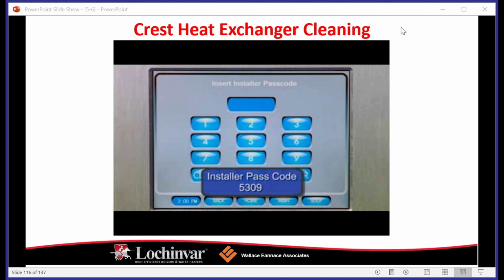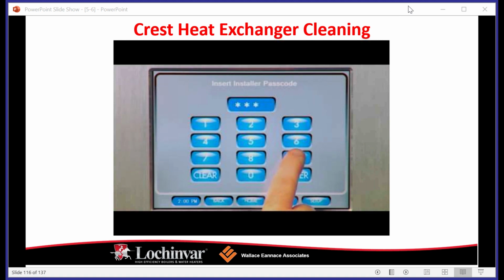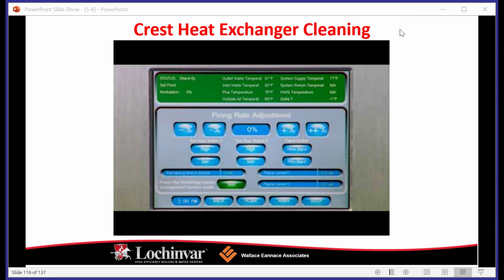A gasket is used to seal between the heat exchanger door and the heat exchanger. Care must be taken not to tear or damage the gasket. If the gasket is damaged or torn, then it must be replaced. Inspect the heat exchanger surface and combustion chamber wall for any soot deposits or dirt accumulation. Using a vacuum cleaner, remove any loose debris from the heat exchanger. Brush the heat exchanger surface, flue tube entry points, and the combustion chamber wall using a nylon bristle brush. Re-vacuum the heat exchanger to remove debris.